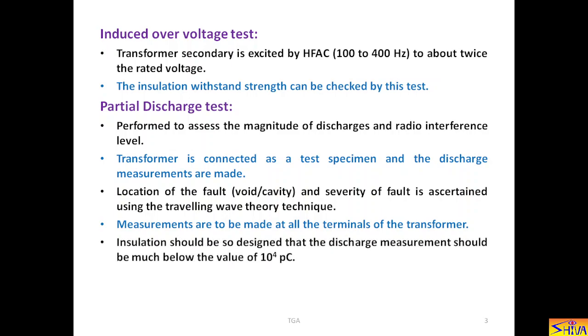Insulation should be so designed that the discharge measurement should be much below the value of 10 to the power 4 picocoulomb. But this is the maximum permissible value.